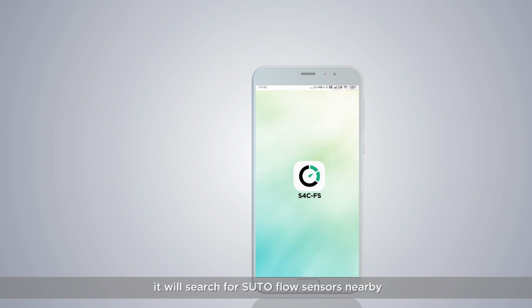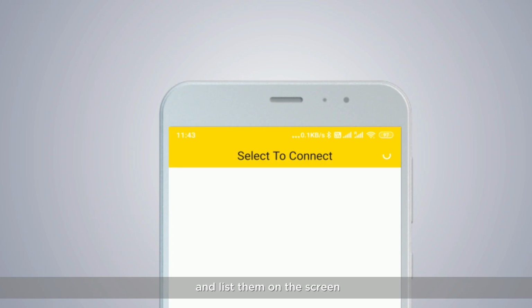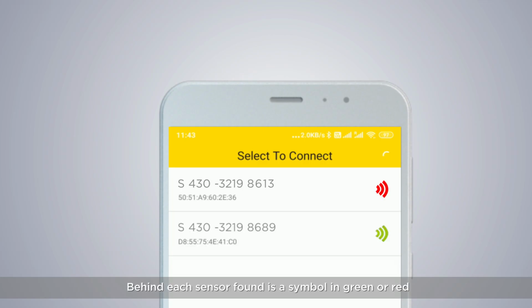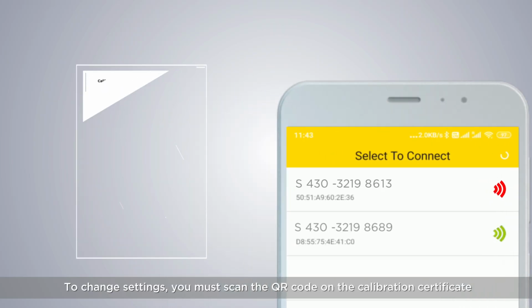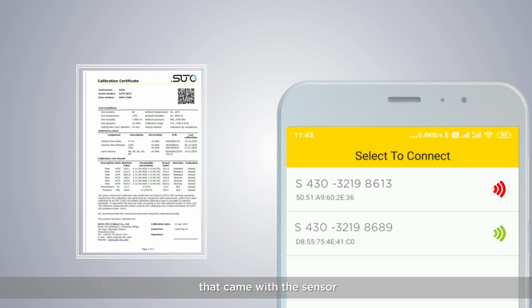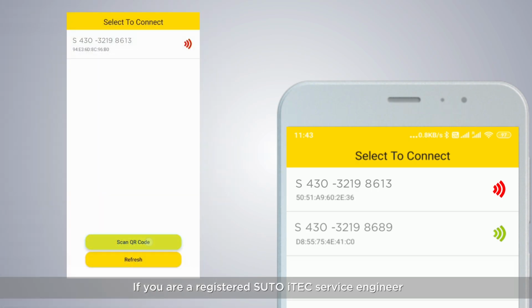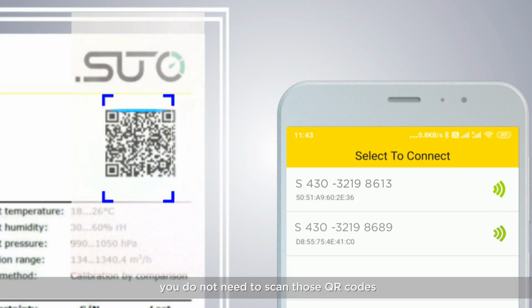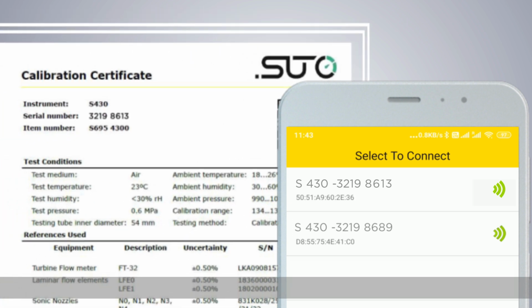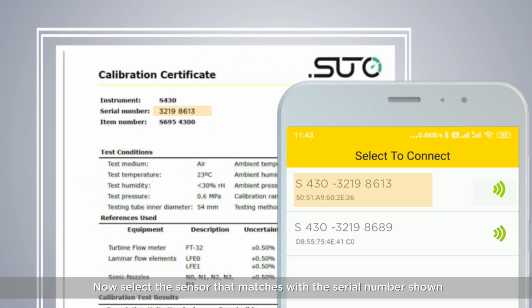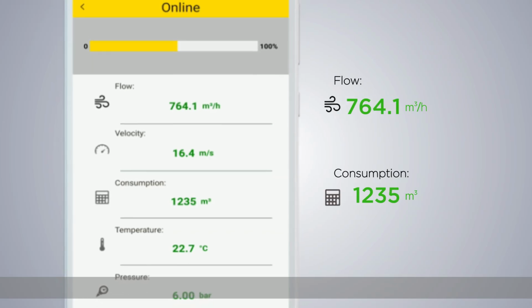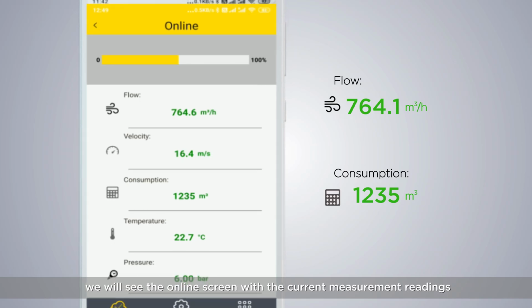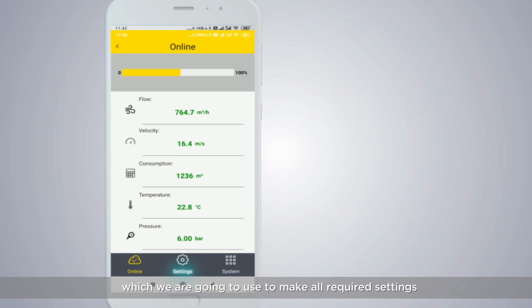After startup, it will search for Suto flow sensors nearby and list them on the screen. Behind each sensor is found a symbol in green or red. Red means you are not allowed to change settings, but you can watch the settings. To change settings, you must scan the QR code on the calibration certificate that came with the sensor. If you are a registered Suto iTech service engineer, you do not need to scan those QR codes. You have full access. Now select the sensor that matches with the serial number shown. After selecting the sensor, we will see the online screen with the current measurement readings. On the lower side of the screen, there is a button for settings, which we are going to use to make all required settings.